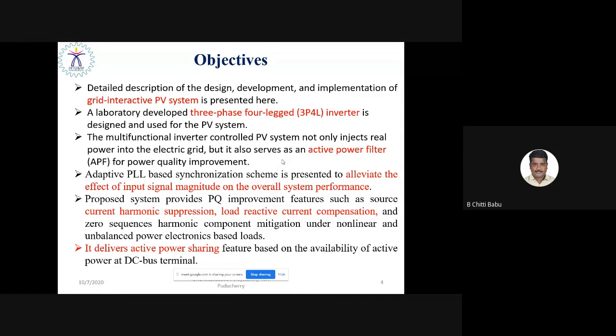And for grid synchronization here, to have a precise control methodology, we have proposed an adaptive PLL-based synchronization scheme, to alleviate the effect of input signal magnitude on the overall system performance. As I told you, the control method that we propose on the grid side converter largely depends on the reference current generation. So whatever technique we propose on the grid side converter, it has to be very precise and it has to be adaptive.